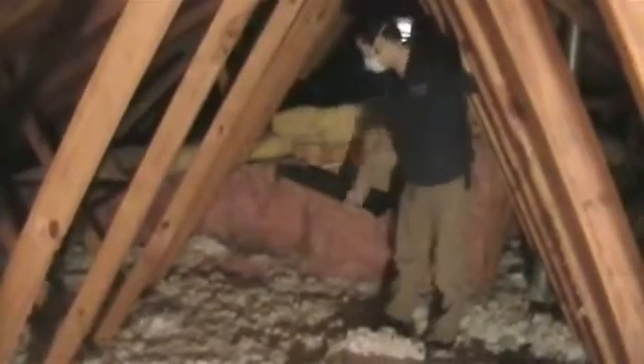The places that we typically find the biggest savings are your basements and your attics. Like I said, there's a lot of things we're looking for when we do these attics. And usually areas that we find a lot of leakage are your exterior walls, because you figure those top plates are also at the edge, and now you've got soffit venting, so that air's coming in, and the first place it can come is right down into there.